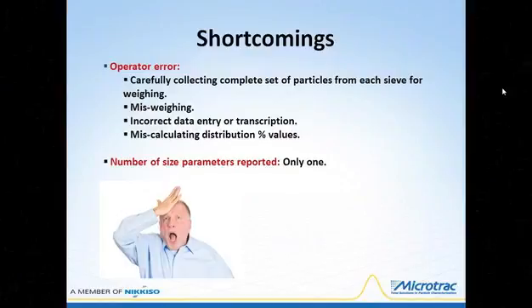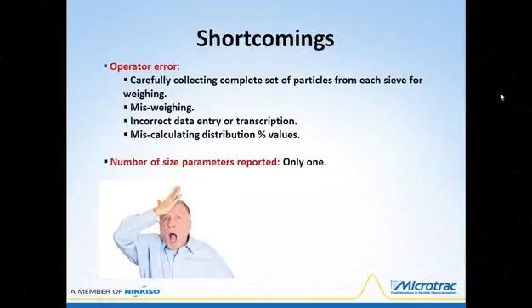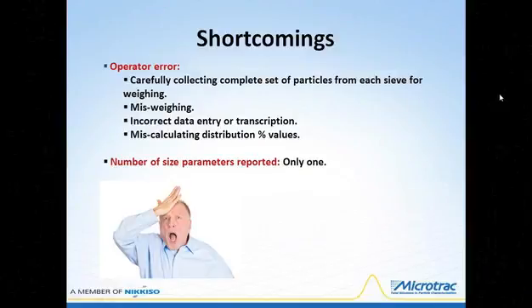This slide is a reminder of some shortcomings of sieve analyses. First is the potential for operator error — particles remaining on each sieve must be carefully collected. Standards state to poke particles stuck in sieve openings into the next smallest sieve retained mass, but this is usually done the other way around. Missed weighing of a sieve fraction is a common error, as are incorrect data entry, transcription errors, and miscalculation. The number of size parameters reported by sieves is only one: a mass percent by size fraction.